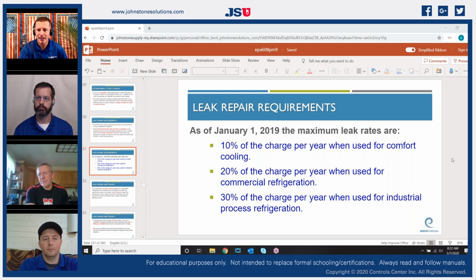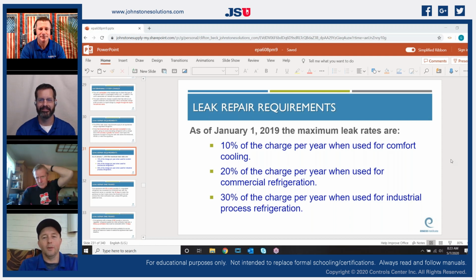Brian, Paul, anything you'd like to add? I would like to mention one thing that you brought up. That scale, if you haven't used it, is pretty awesome. Yes, it is. I did some testing with it, and I think you did too. It uses the GPS location off of your phone to tag the weight of the refrigerant. So when you set your tank on there, zero everything, and start pulling refrigerant out of it, it immediately tags it to the GPS location where you're at.